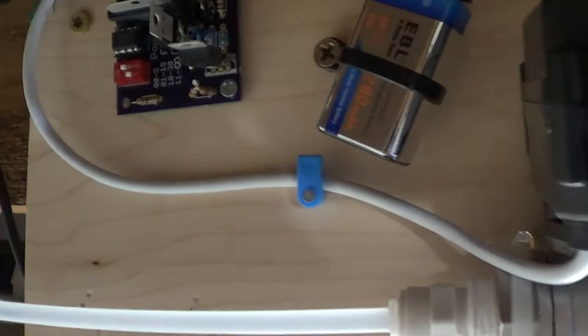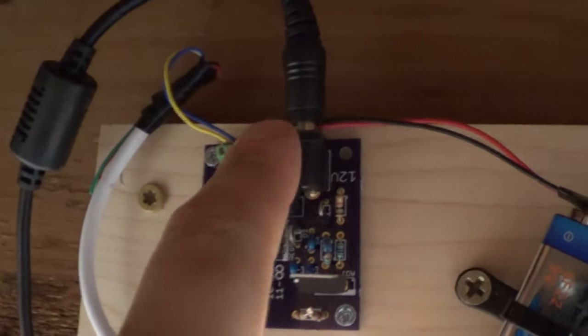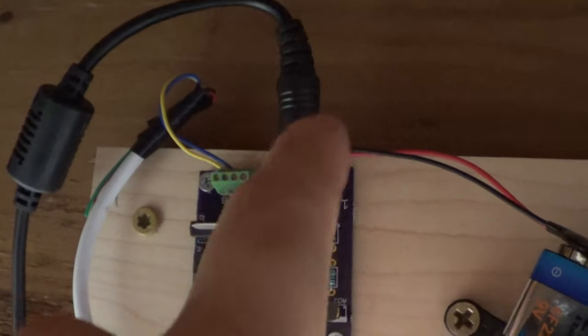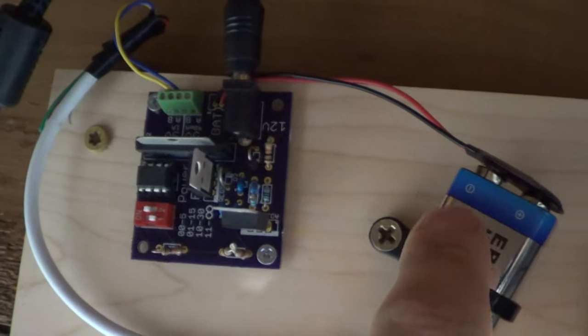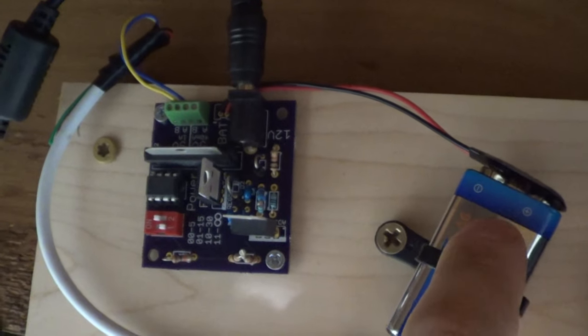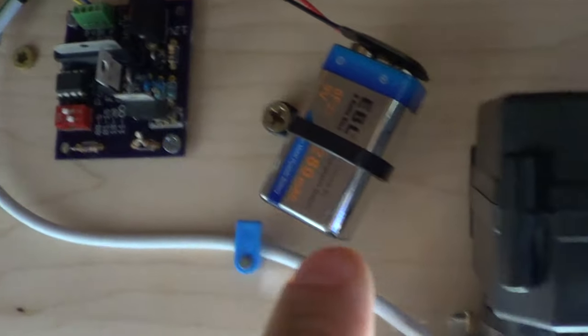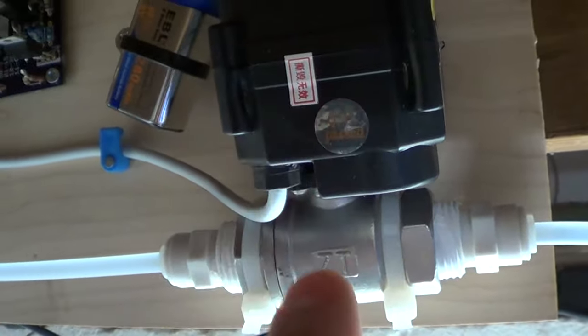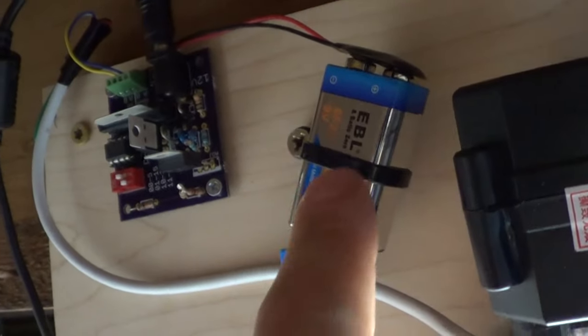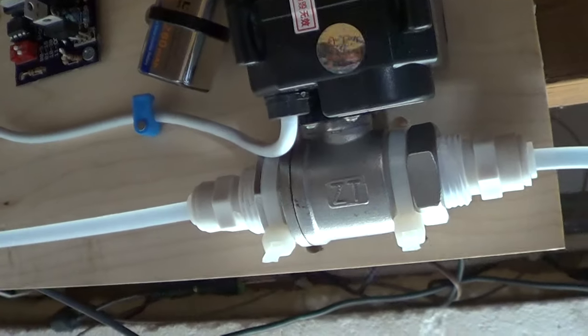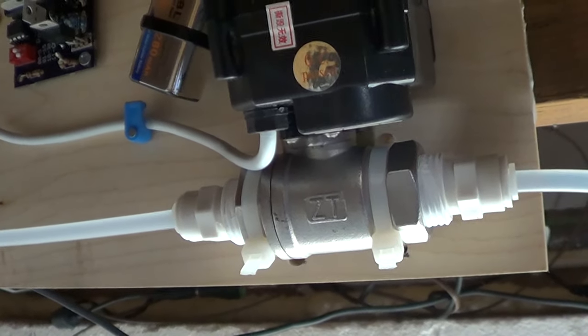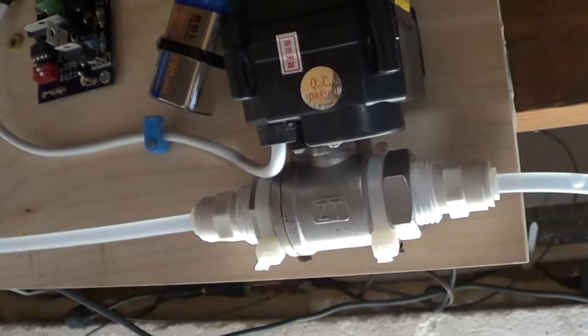In the case of a power outage, what will happen is all of a sudden it won't get 12 volts from here, and the only source of power it gets is the 9 volts from the battery, and then it tells this motor to shut using the power that is remaining in this battery. And this motor only has to turn on for about five seconds to shut that valve, and then it's off.